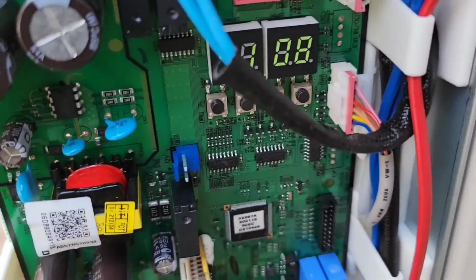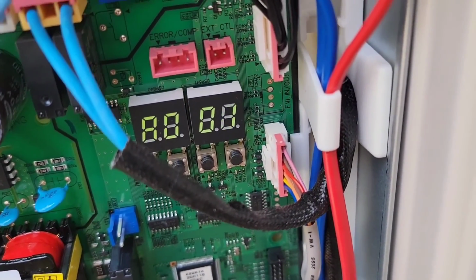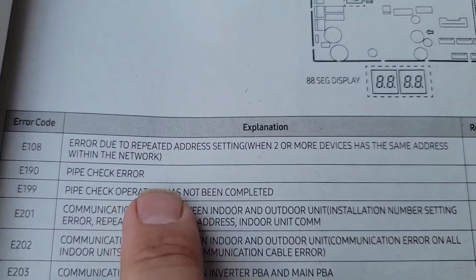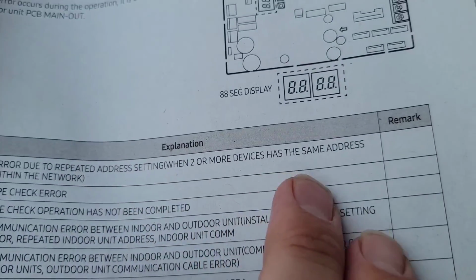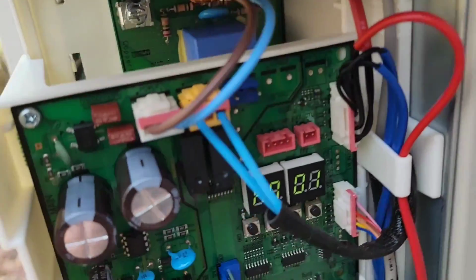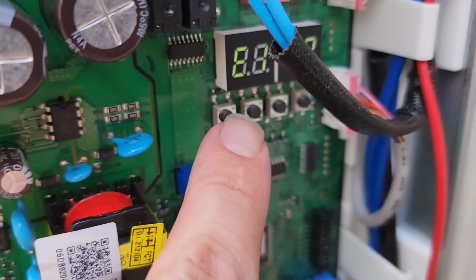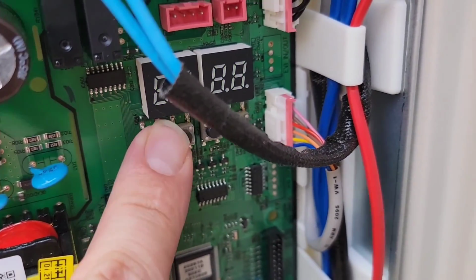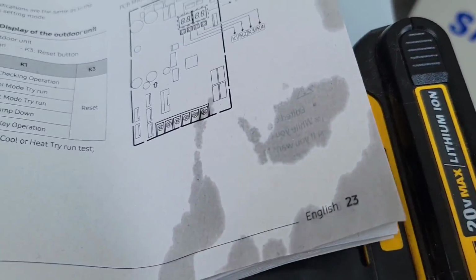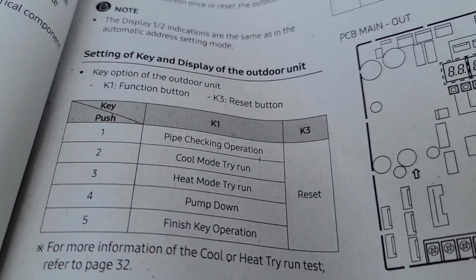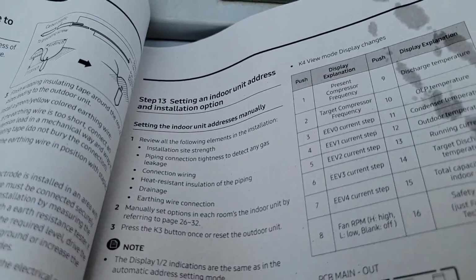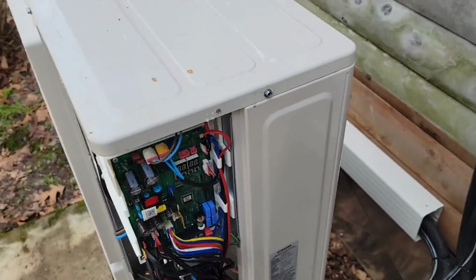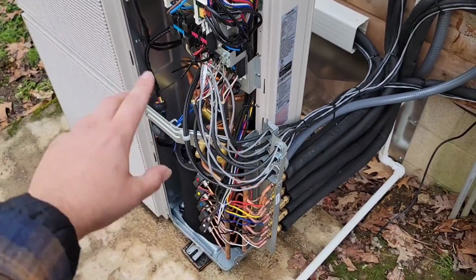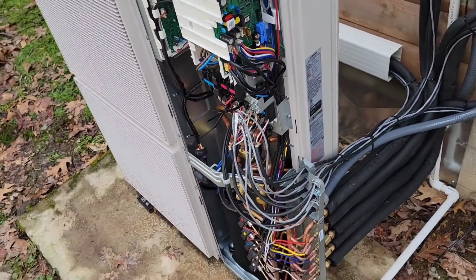Breaker is on. Oh, it's got a little code. E108. Okay, no big deal. Error due to repeated address setting when 2 or more devices have the same address within the network. So what do we do now? We just hit the K1. Page number 23, pipe checking operation. K1. Okay. Now we're going to wait, and it's hopefully going to be able to recognize all of our indoor units and not have repeated addresses.